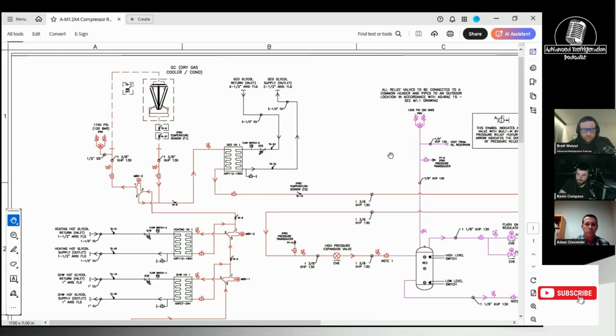All your PID loops on the fan control have to be really slow. The challenge with that is, what do you do in the summertime? You start to rack up and you start it up, and now the fan response, the integral is so wound up that you just get no response, and you end up going fast recovery several cycles until things start to smooth out. The same thing happens when you go into split. So if you split and your fans don't recover quickly enough, then you can run in that same situation.